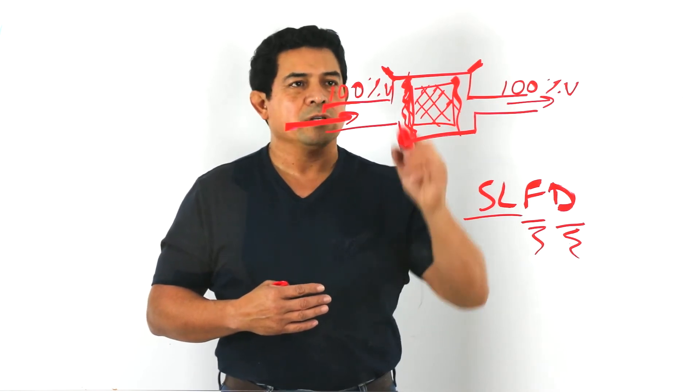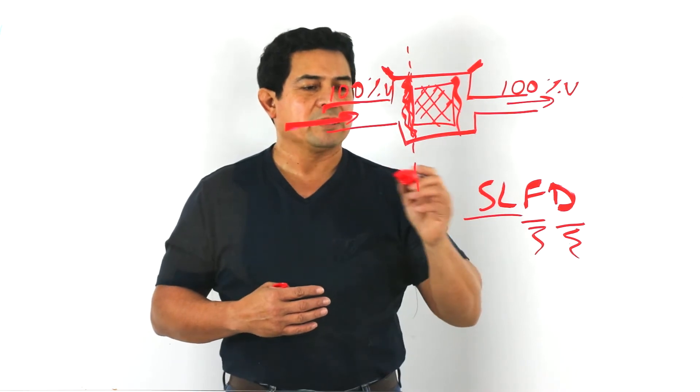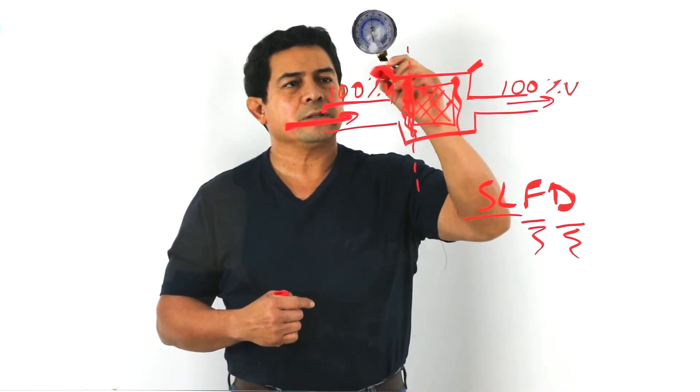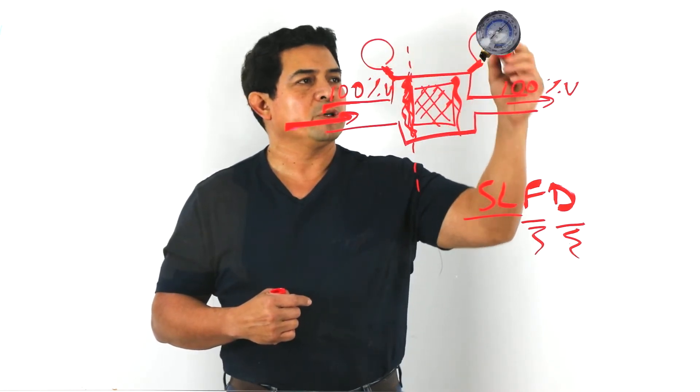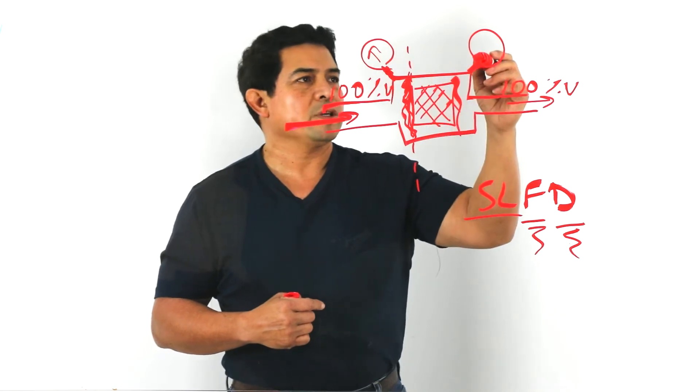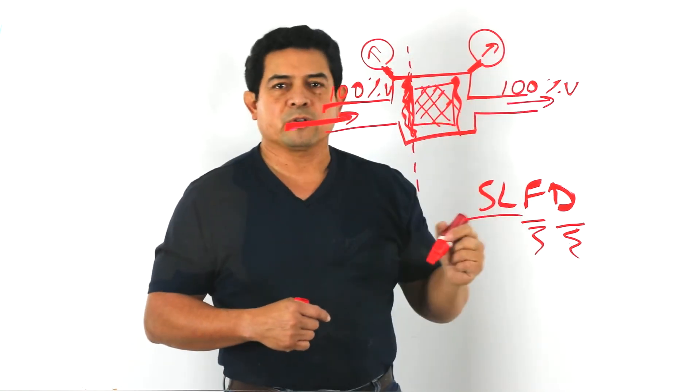Because you have a restriction, your pressure is going to be different on this side than it is on that side. These connections right here, they are so that you can put a gauge on there. So now we're going to read a pressure here, read a pressure here, or you can take the pressure here and then move it over to the other side.